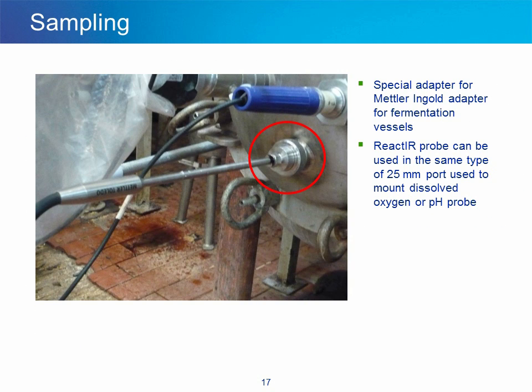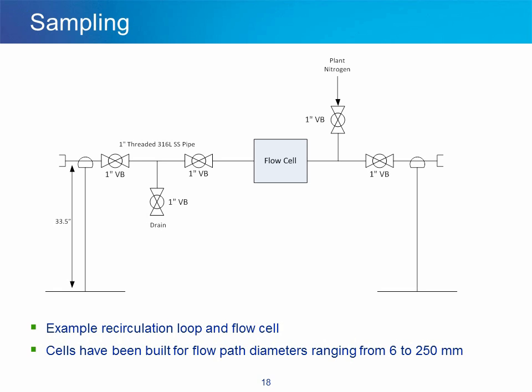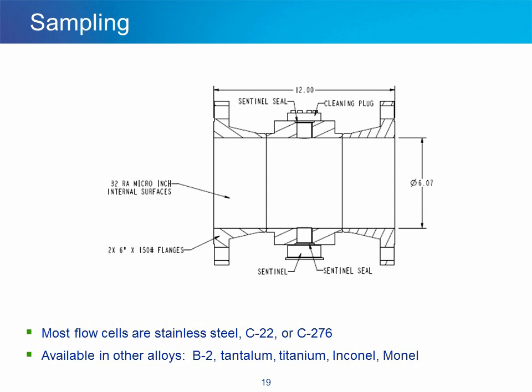A special adapter can be embedded in a Mettler-Ingold adapter for fermentation vessels. Thus, the React-IR probe can be used in the same type of 25 millimeter port commonly used to mount a dissolved oxygen or pH probe. Turning our attention to flow cells, we see an example of a recirculation loop in flow cell setup. Cells have been built for flow path diameters ranging from 6 to 250 millimeters. Most flow cells are made from stainless steel, C22, or C276, but are available in other alloys such as B2, Tantalum, Titanium, Inconel, and Monel.